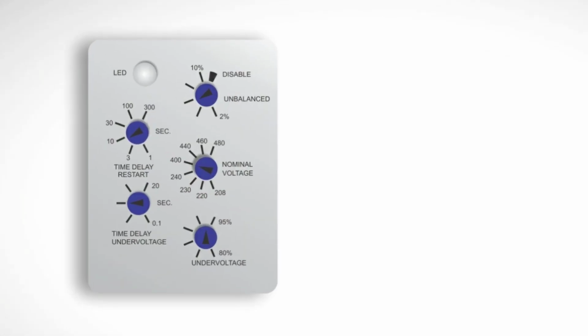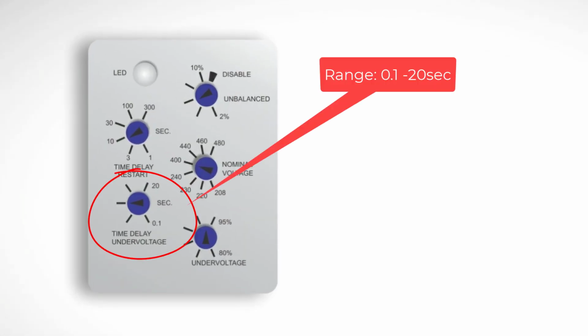This is the undervoltage delay timer. Range 0.1 to 20 seconds. It prevents nuisance tripping during short voltage dips and temporary fluctuations. Example, set 2 seconds, ignores very short drops.